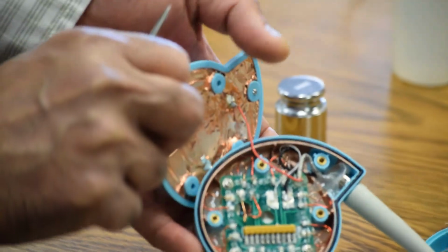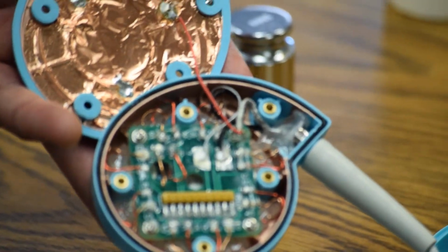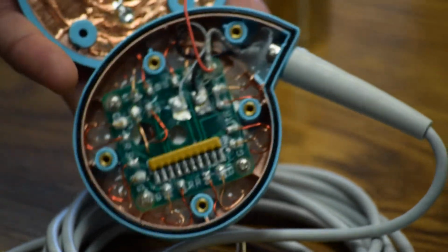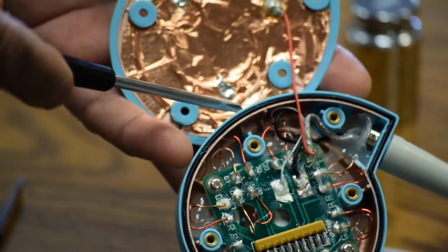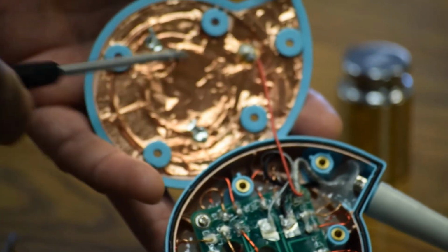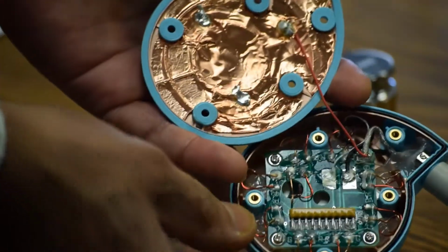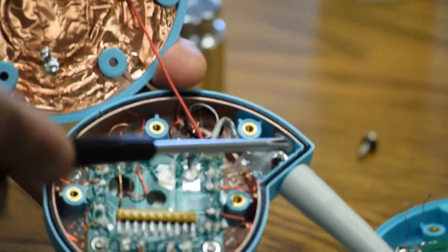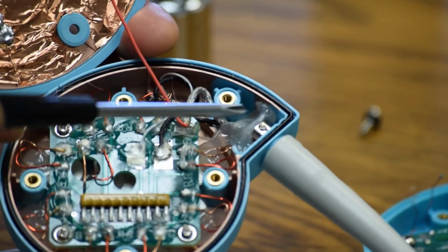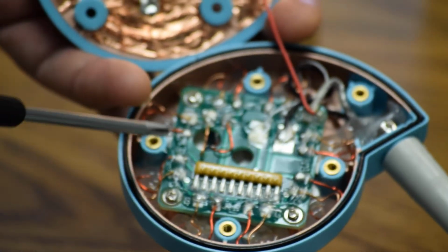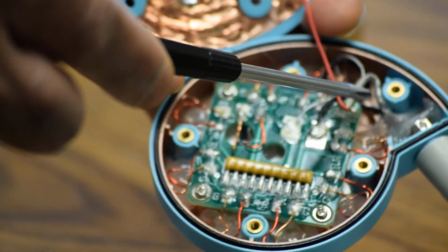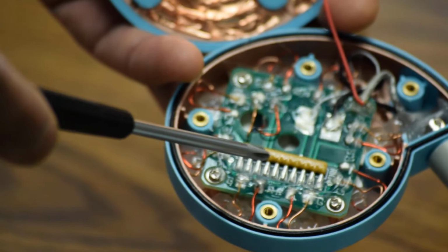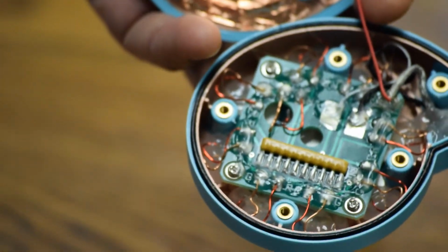This is the transducer completely open. Again, non-compliant process here. In an original transducer you will never find the foils. The foils have been stuck inside. See the silicone, acidic silicone poured all over. Cable is glued to the bottom case plastic, which is not the case in the original GE transducer. All over is silicone, very dirty work. Crystals are non-OEM. This transducer is never going to work to GE specifications and comply with any regulations.